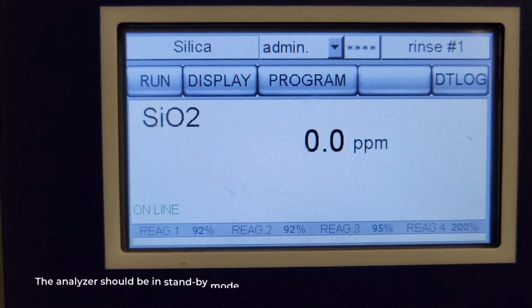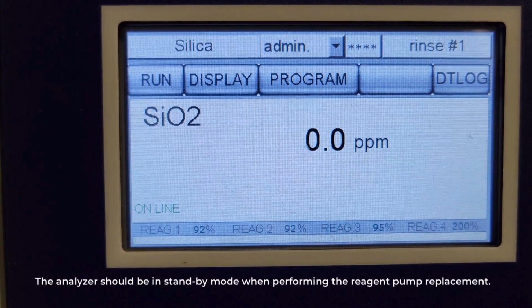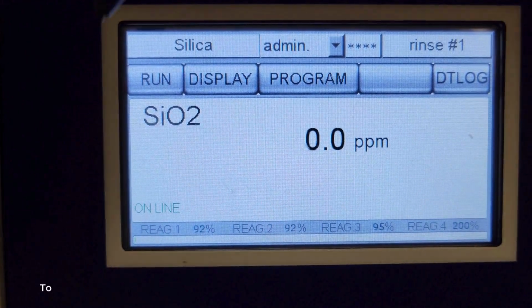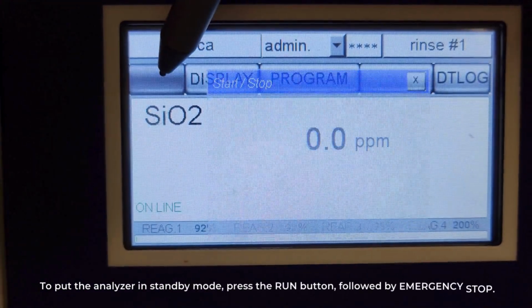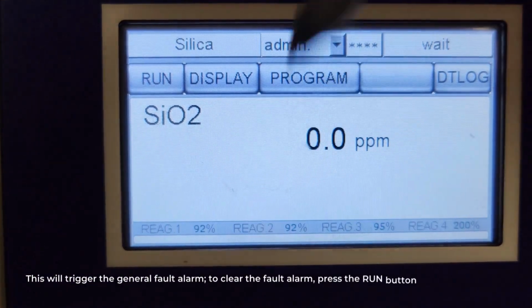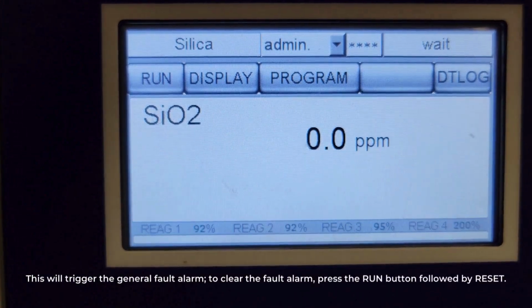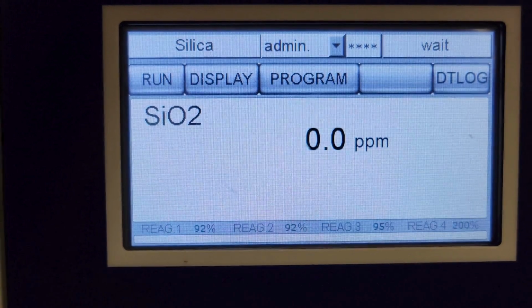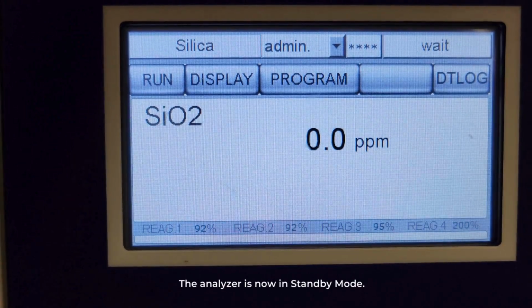The analyzer should be in standby mode when performing the reagent pump replacement. To put the analyzer in standby mode, press the run button, followed by emergency stop. This will trigger the general fault alarm. To clear the fault alarm, press the run button followed by reset. The analyzer is now in standby mode.